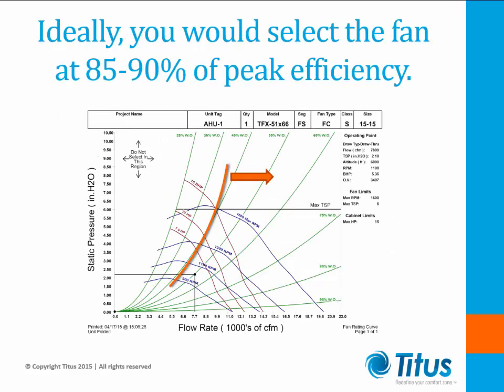In this slide, what we're trying to show is the ideal location for fan operation within the units. A good practice is to select a fan with an operating point that is slightly to the right of the peak static efficiency. This is represented by the orange line on the graph. Selecting the fan at 85 to 90% peak static efficiency allows the fan to remain stable even if filters begin to load up.